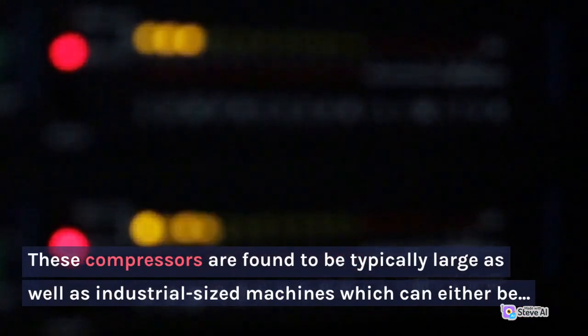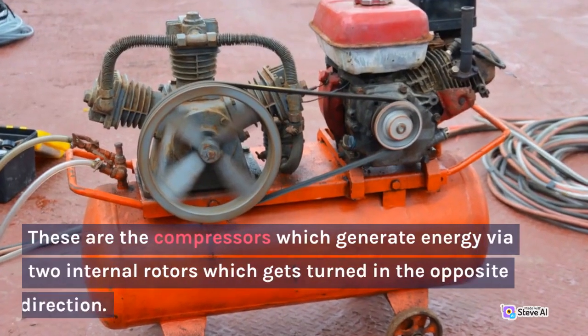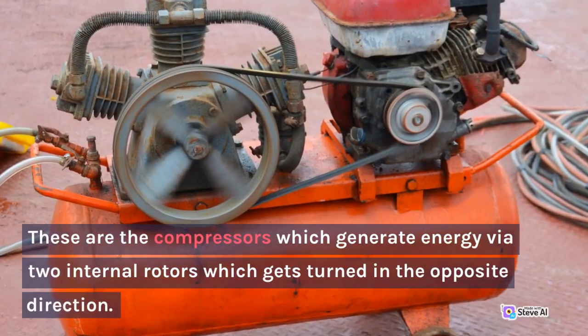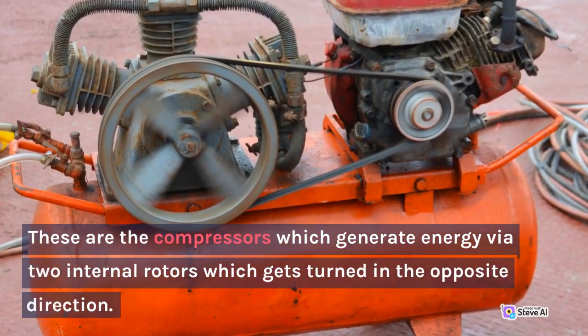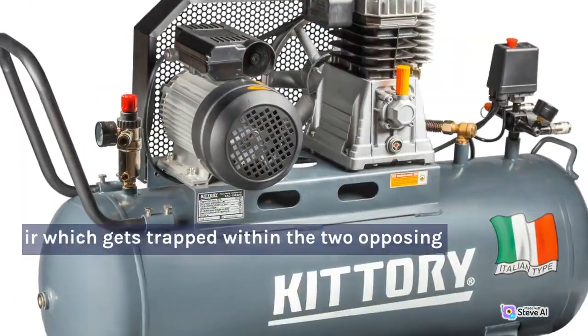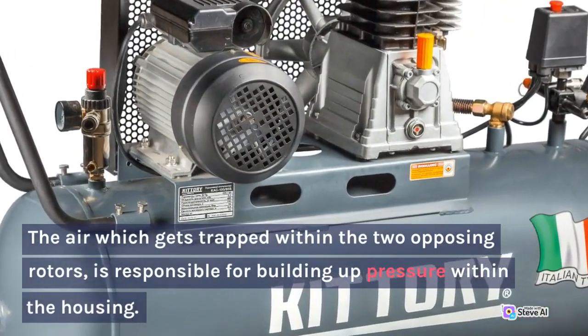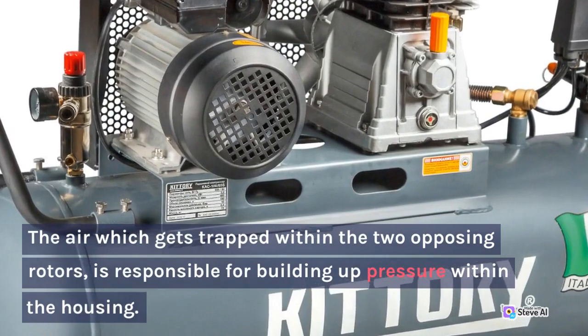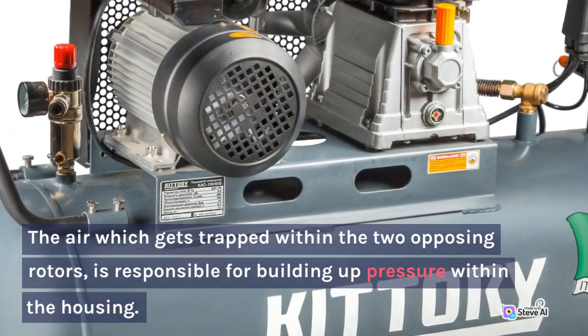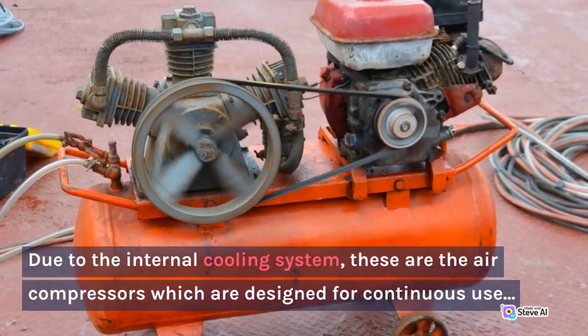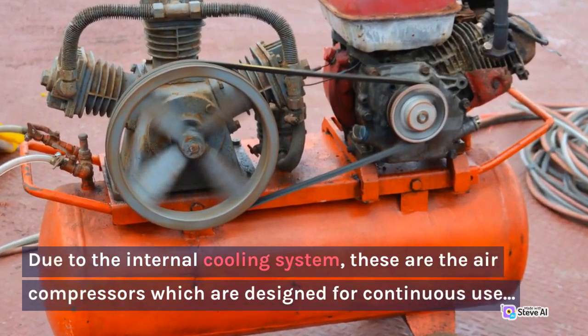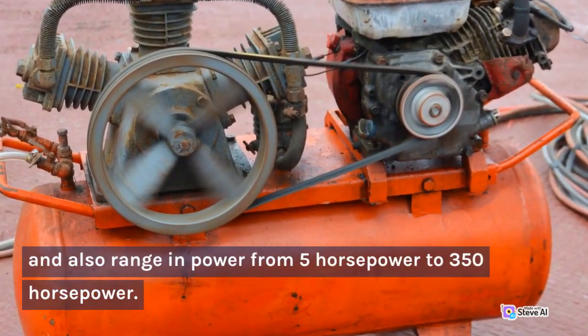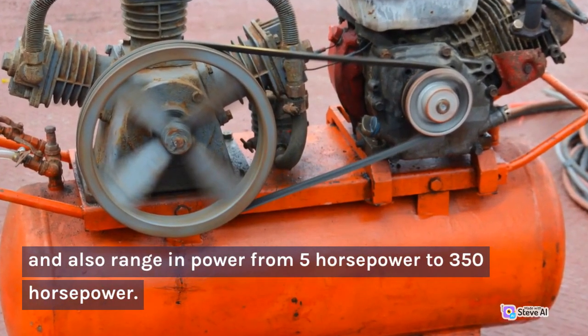These compressors are typically large, industrial-sized machines which can either be lubricated with oil or can even run oil-free. These are compressors which generate energy via 2 internal rotors which get turned in opposite directions. The air which gets trapped within the 2 opposing rotors is responsible for building up pressure within the housing. Due to the internal cooling system, these air compressors are designed for continuous use and also range in power from 5 horsepower to 350 horsepower.